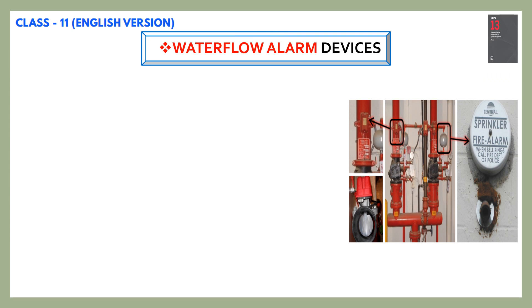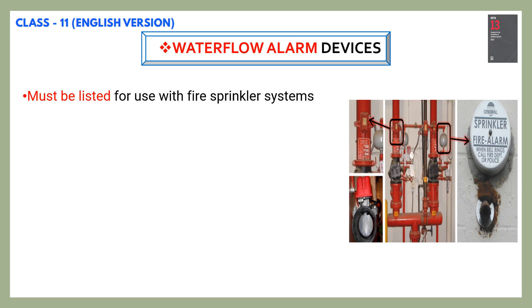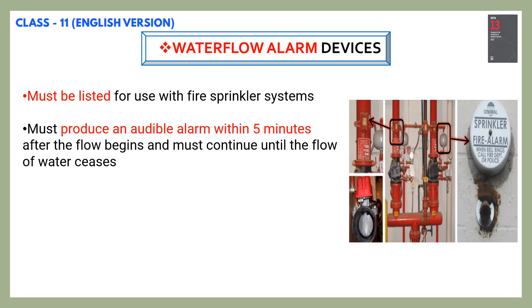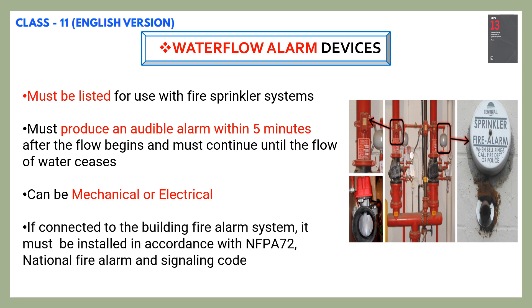Let's go through water flow alarm devices. Water flow alarm devices must be listed for use with fire sprinkler systems. They must produce an audible alarm within 5 minutes after the flow begins and must continue until the flow of water ceases. Water flow alarm devices can be mechanical or electrical. If connected to the building fire alarm system, they must be installed in accordance with NFPA 72, which is the standard for the National Fire Alarm and Signaling Code.